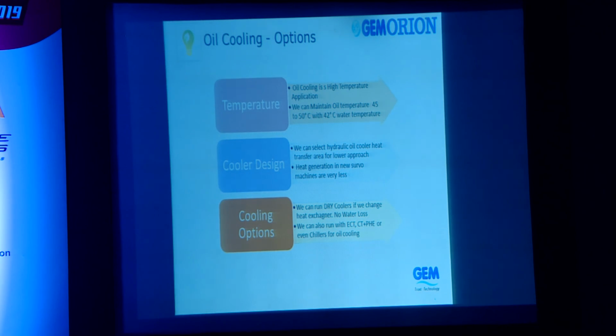So when we talk of the oil cooler, it is a high temperature application, and we have to maintain about 45 to 50 degrees, which can be done by water at 42 also. We need not use water at 32 or 33 from the cooling tower directly, or from a combination of 34, 35. So directly we can give a dry cooler. Plus, to achieve this, we will have to select the hydraulic oil cooler heat exchanger area slightly larger, so that we can get the same desired oil temperature when the oil inlet temperature is high.